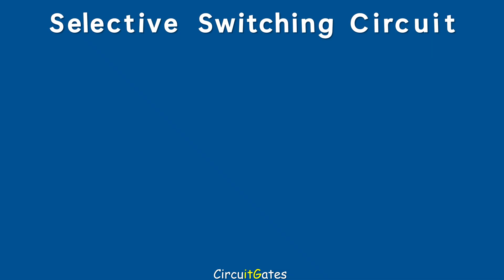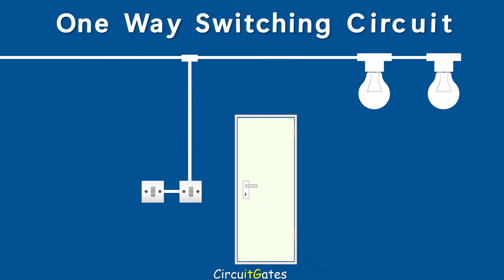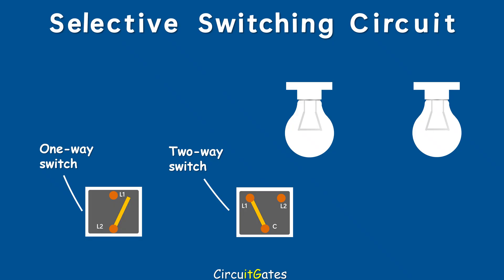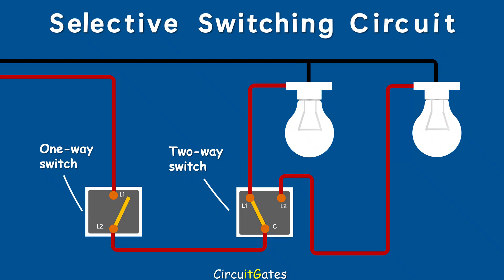We have another light switching circuit called the selective switching circuit, which makes it easy to provide two levels of lighting in certain circumstances. A selective switching circuit consists of a one-way switch and a two-way switch. The live wire from the supply is connected to the one-way switch, then goes to the common terminal of the two-way switch. One lamp is connected to terminal L1 of the two-way switch, and the other lamp is connected to terminal L2. When the one-way switch is off, none of the lamps are illuminated. When it is on, one lamp will illuminate depending on the position of the selector of the two-way switch.